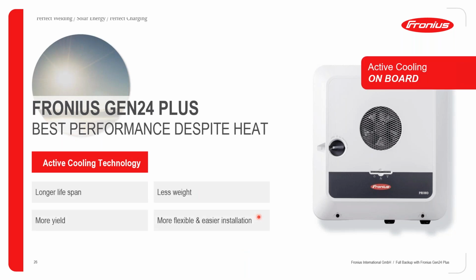With the Gen24 Plus series, you also get the active cooling technology, and this can give your system a longer lifespan. Okay, so we use a fan in our inverter. Okay, so we use a combination of a fan that is regulated, and we also use a heatsink. So the heatsink lies directly beneath the fan, and the heatsink and the fan in combination ensure that we can operate in a really wide range of operating temperatures before system derating starts to happen. And again, this will ensure that you get more yield, and it also ensures that you get more flexible and easier installation as well.